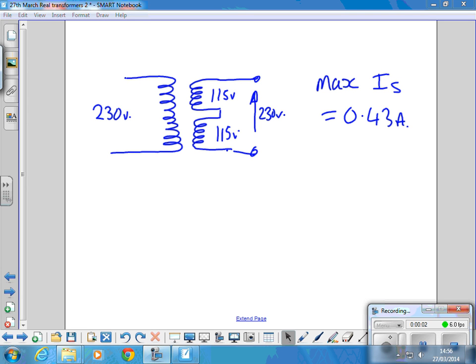This is a transformer with the primary side. You can either input 400 or 230 volts. And we've got two windings on the secondary side of 115 volts each, and you can link them together to make 230. So what we're going to be doing, at the moment anyway, is using it in 230 volt mode as an isolation transformer effectively. So we've effectively got 230 volts in and 230 volts out that provide an isolation.